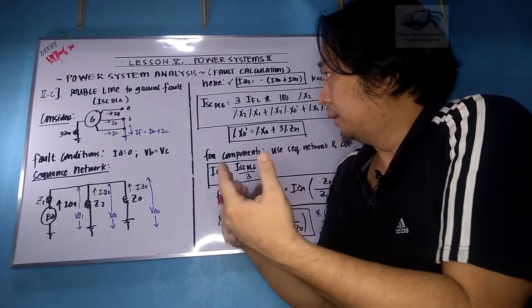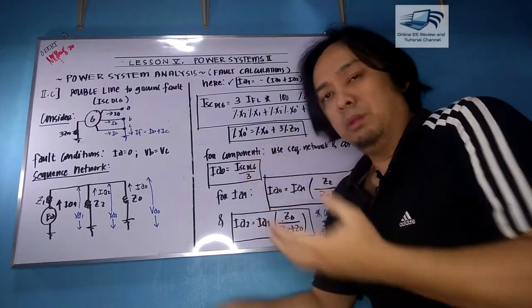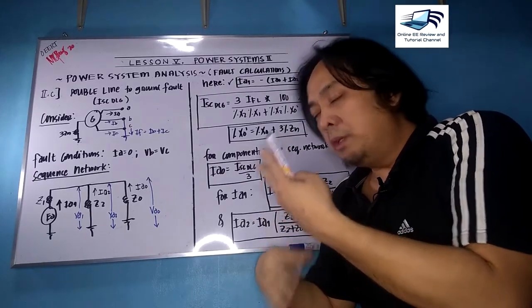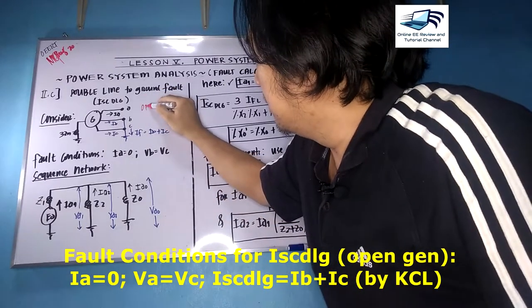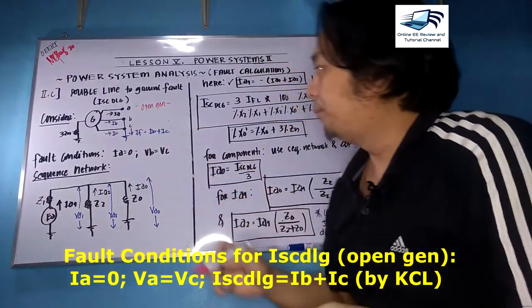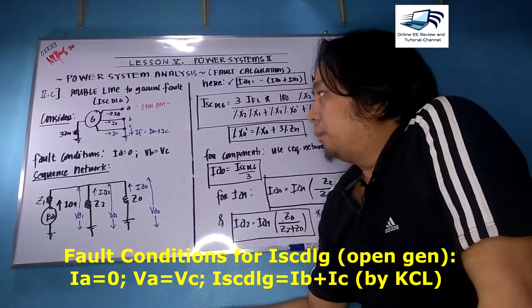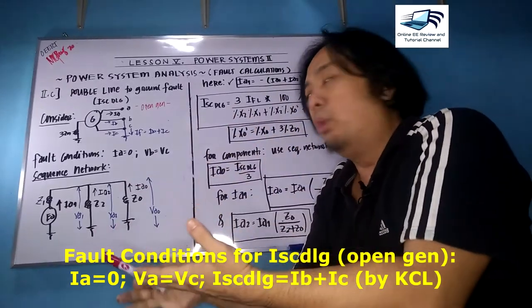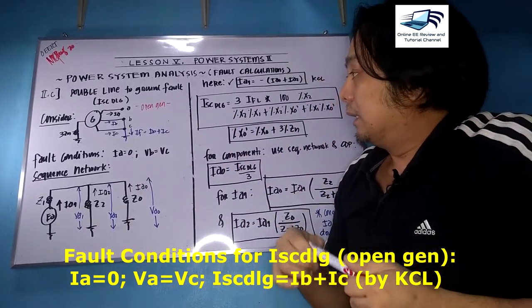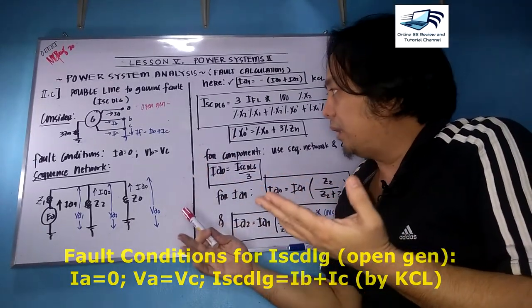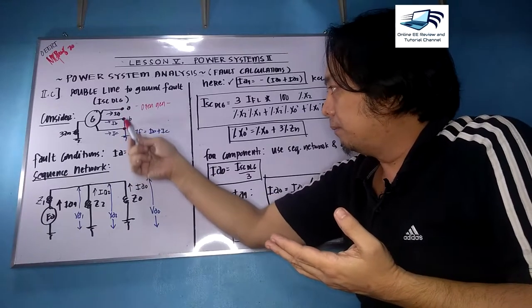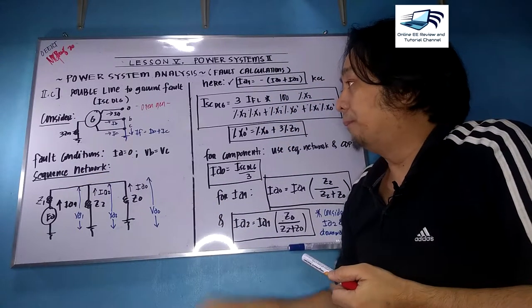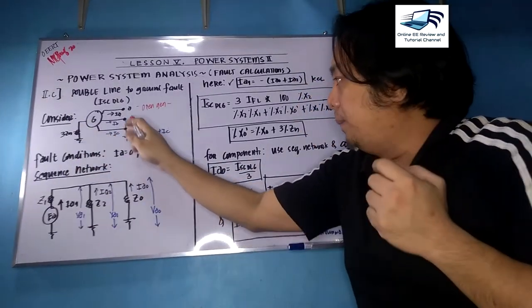We will now discuss the double line-to-ground fault, or ISC DLG. We consider again an open generator. This is similar to 2B but the difference is phases B and C are grounded, meaning they are short-circuited and also grounded to the neutral. Z0 prime equals Z0 plus 3ZN, where ZN is the neutral impedance.